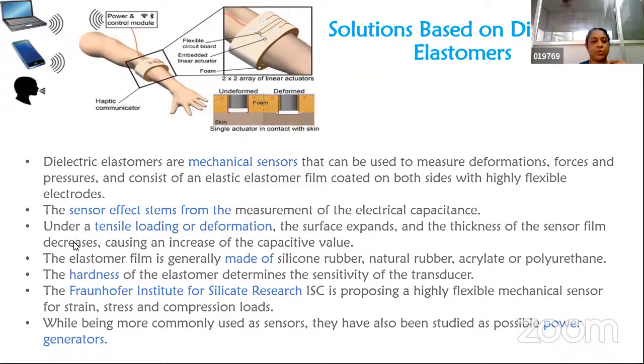So under the tensile loading deformation, the surface expands and thickness of the sensor film decreases, causing an increase in the capacitive value.